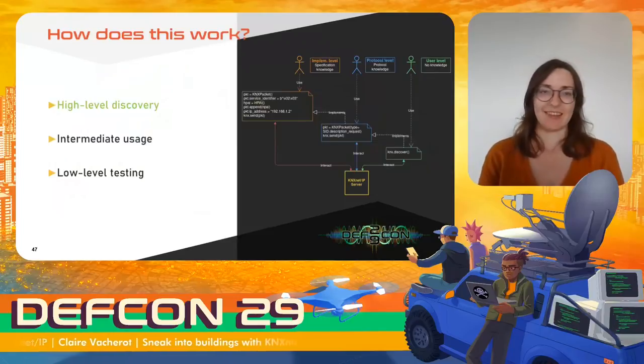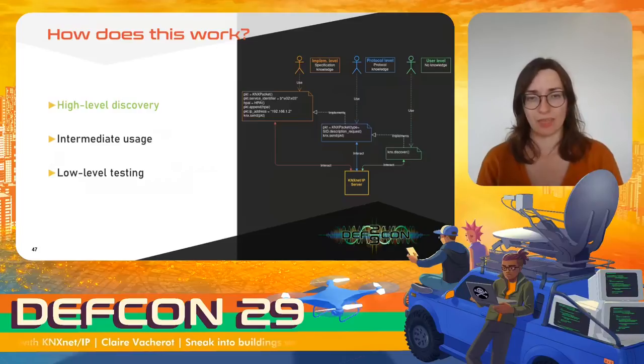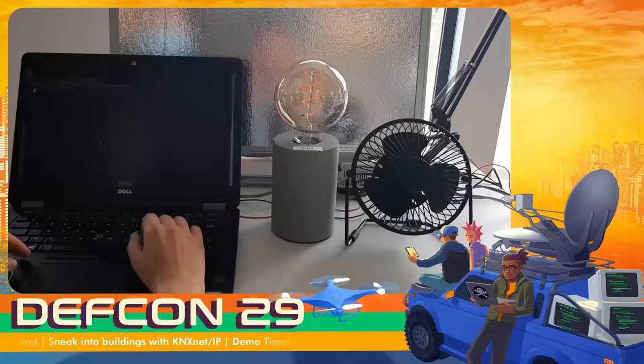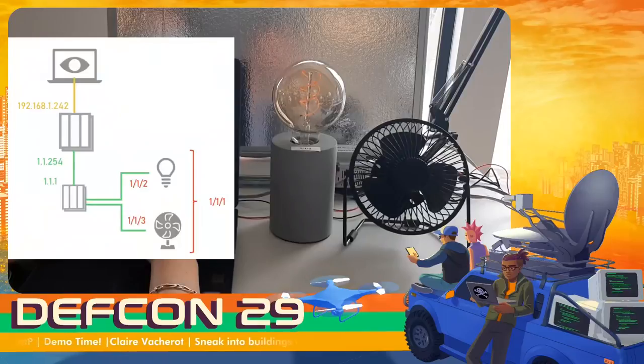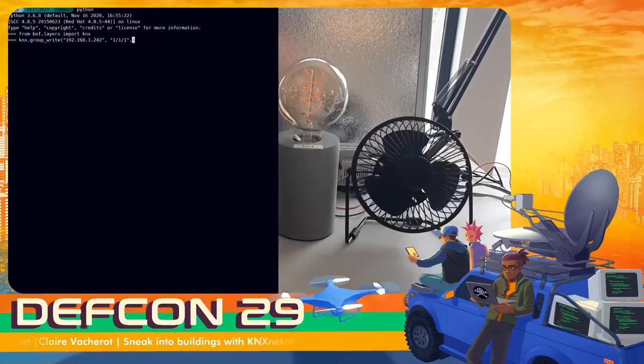BOF can be used for discovery, basic interaction, and advanced testing. The highest level requires no knowledge about the protocol — there are functions that perform basic operations on KNX installations. For example, in my test setup here, I want to turn on a light and fan linked to a switching actuator connected to an IP gateway on the local network. The actuator is subscribed to group address 1/1/1 for the switching operation. Writing value 1 to that group address using the GROUPWRITE function turns them on.